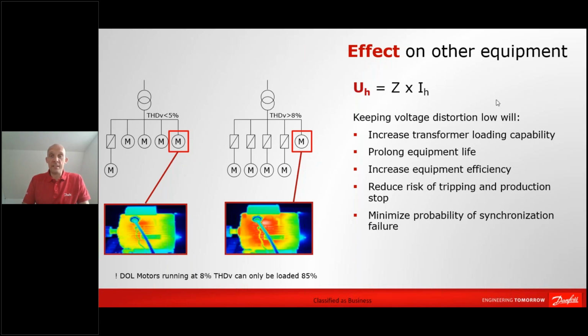You can, of course, always try to reduce the current distortion to a minimum, and that will help you on the voltage distortion, but it's just a very costly way of reducing harmonics, and in many cases, it will actually not help you. It'll just make your installation more expensive, and it'll add more equipment to your installation. That means that the installation is getting less reliable, and there is a tendency of products failing faster when you have more equipment in your installation. So the best way to reduce harmonics and ensure that you're not getting into harmonic issues is actually by doing analysis of your installation. You need to go in and say, is it safe for me to run under these circumstances that I have?